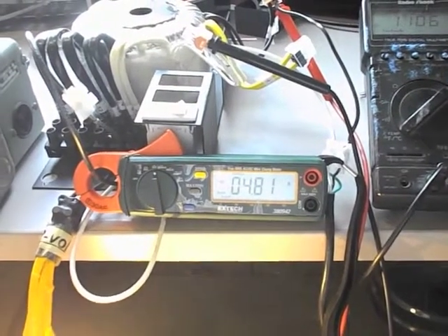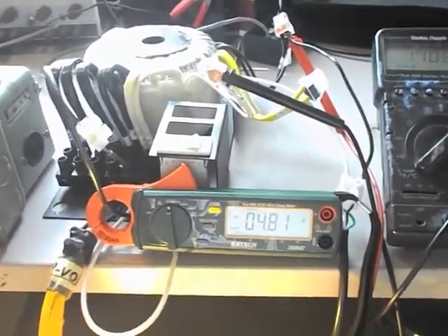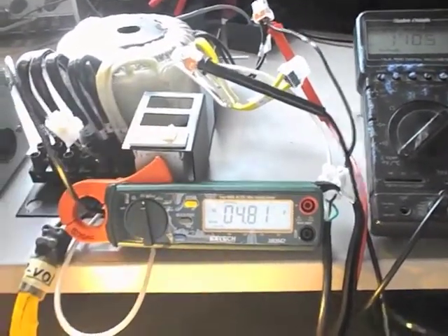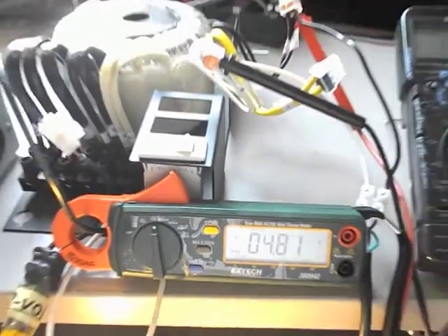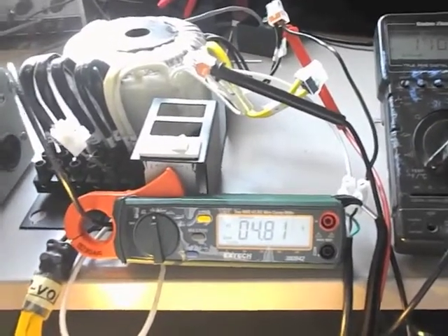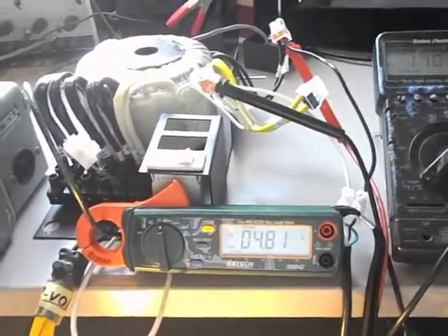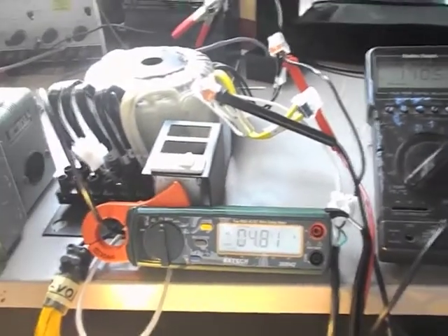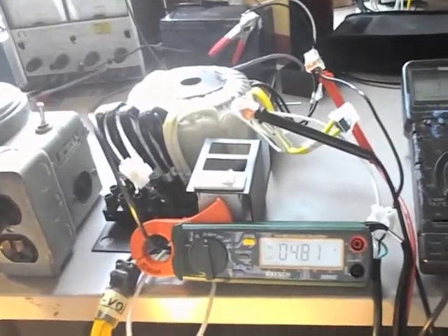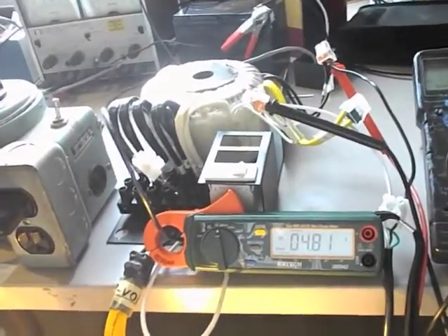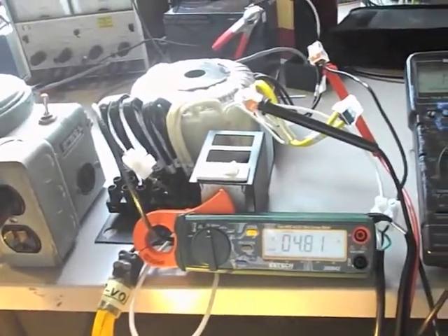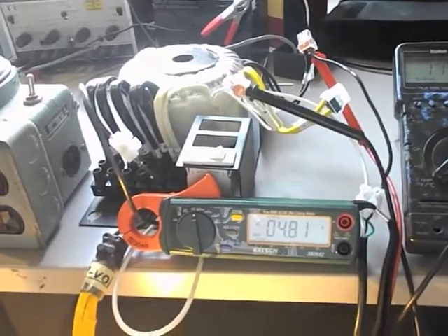This is AC voltage, and I put it on a variac here so that I could boost it. Now this is a 5 amp breaker, you'll see right there, and a 5 amp breaker is calibrated where it has a little bit of leeway, but it is calibrated to trip when it sees more than 5 amps. If it's a short circuit, it will trip immediately. If it's an overload, it has a range of a period of time where over a certain percentage rating it will take a certain amount of time to trip. But if you exceed 5 amps, it will eventually trip.